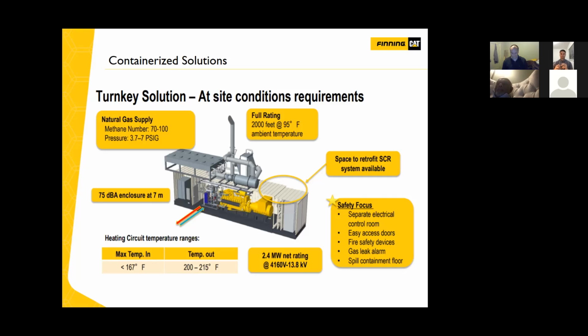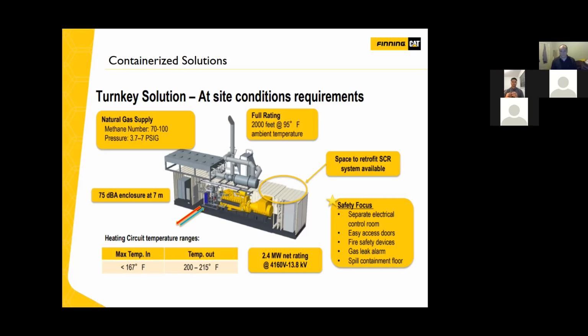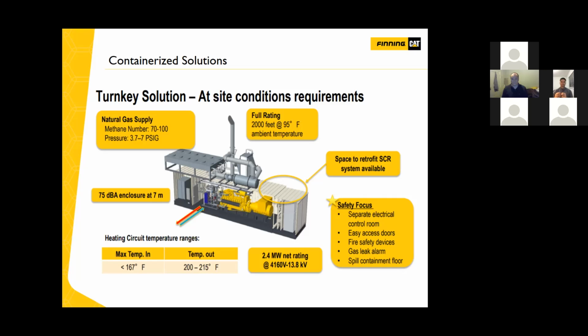On a lean burn natural gas gen set, you only have one choice, and that's a wet urea dosing system, because of the excess oxygen in the exhaust stream. A lean burn gen set is highly efficient, so we have excess oxygen mixed with the fuel, meaning oxygen comes out the exhaust stack. Anytime it's above 4%, you cannot use a non-selective catalyst; you have to use a wet urea system. There's also carbon monoxide and an oxycat in addition to that.